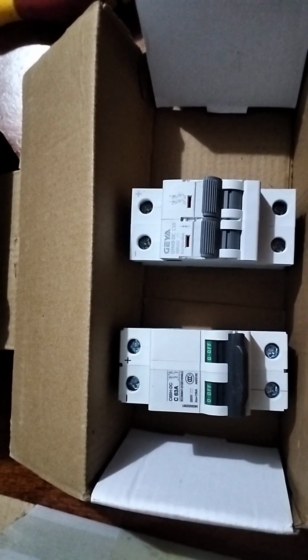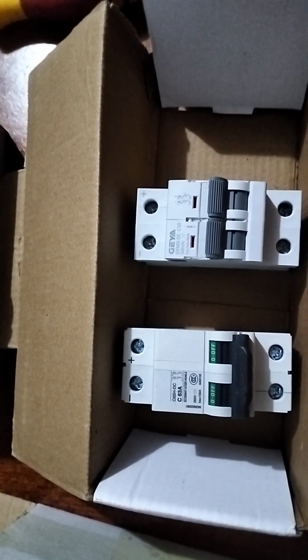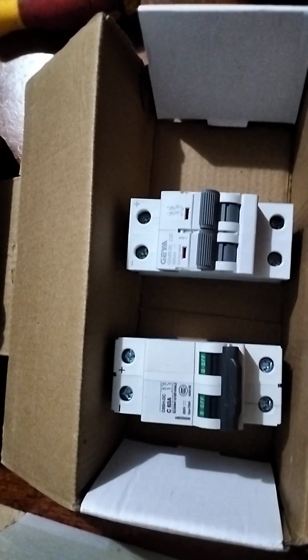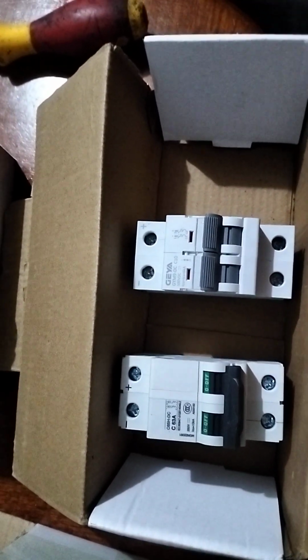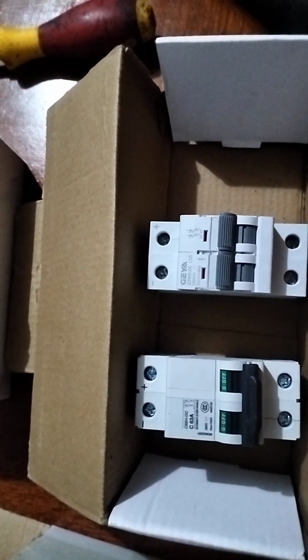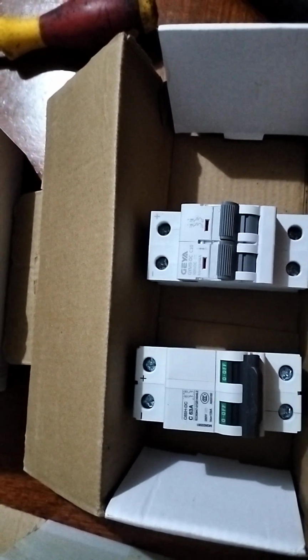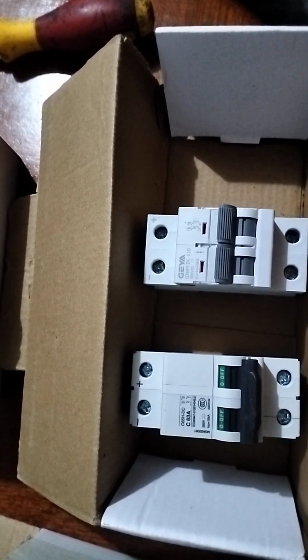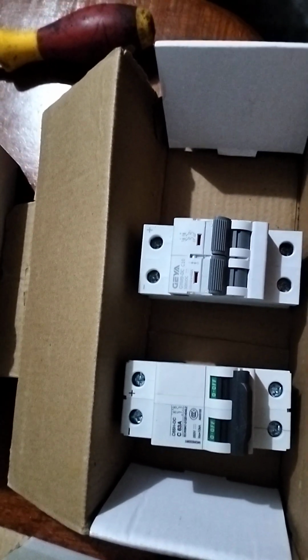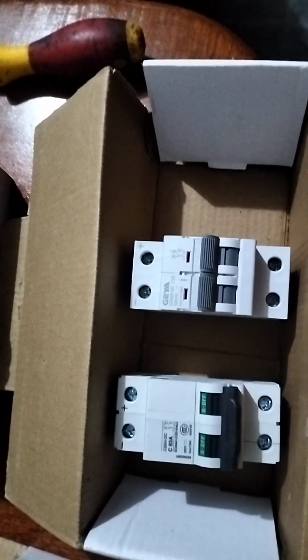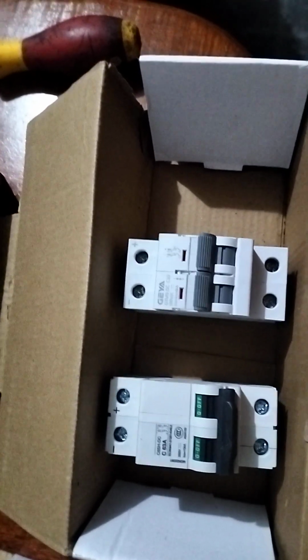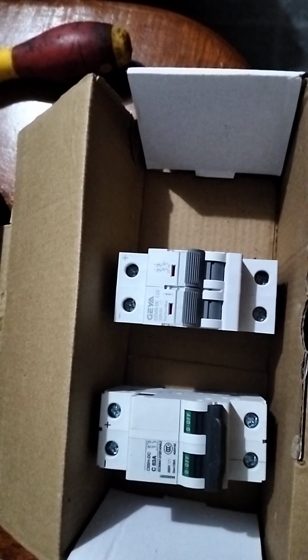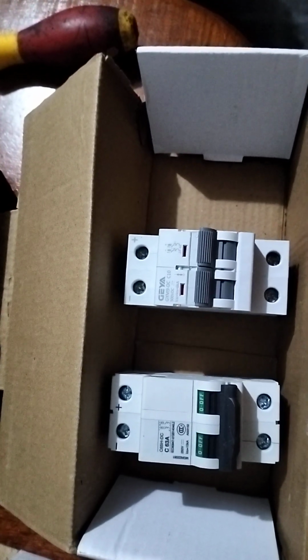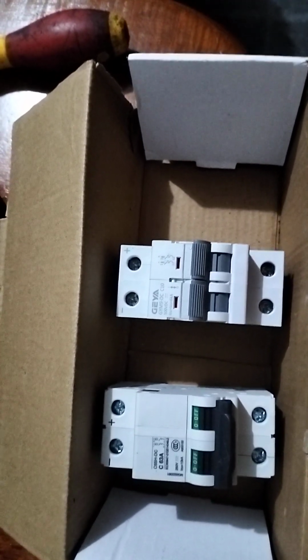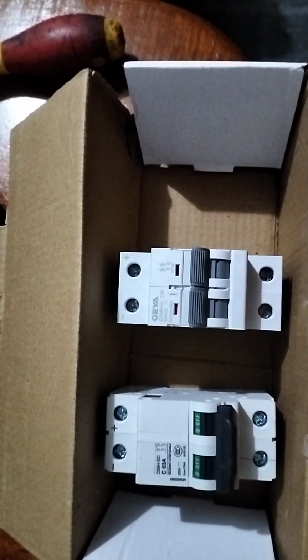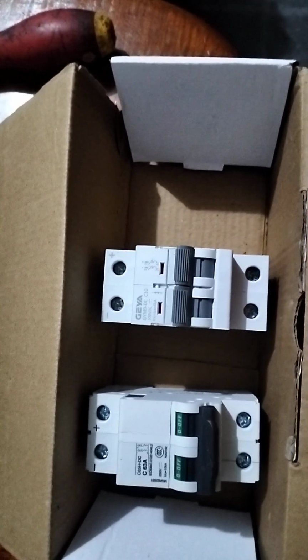The double pole circuit breaker on the left, it's a C-curve, it's 63 amps and it's DC and it's fed from the top. So if you're running a battery, you'd put the battery leads into the top, your positive on the right, negative on the left obviously, and that one's rated for, like I said, 250 volts. I'd only use that on low voltage, probably 50 volts. The one on the right is much higher rating. That's a GEYA, that's 500 volt DC, once again fed from the top. I wouldn't use that as an isolating switch. I'd use that purely as current protection.